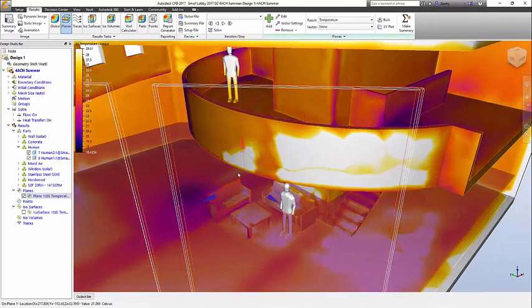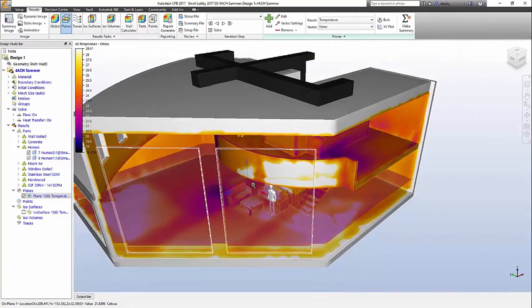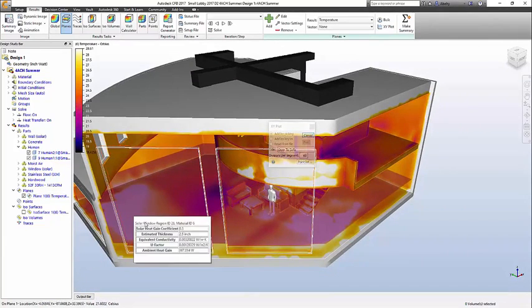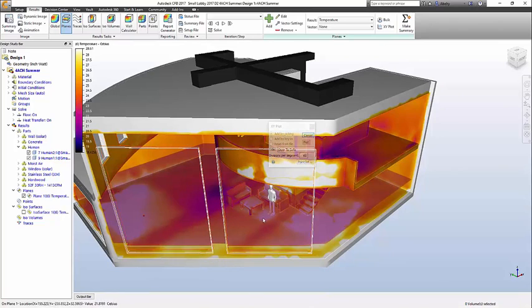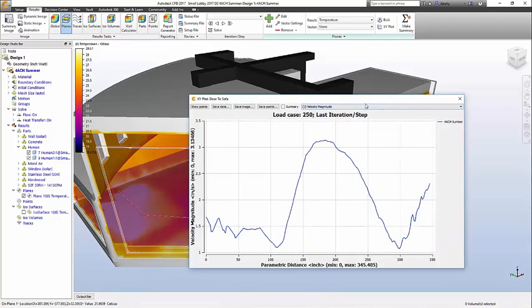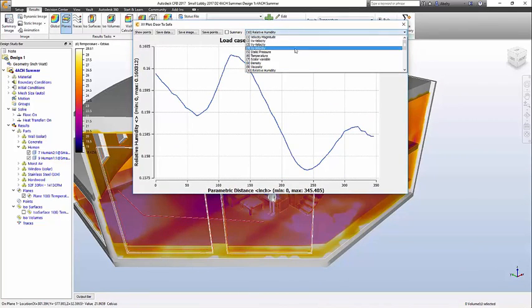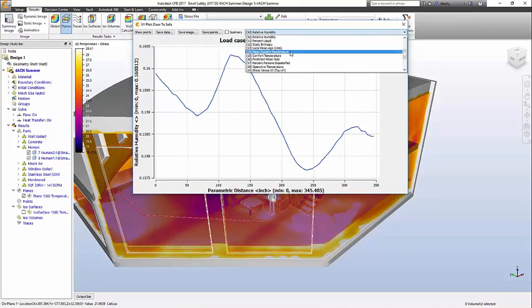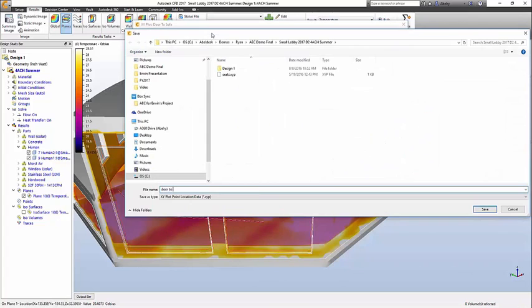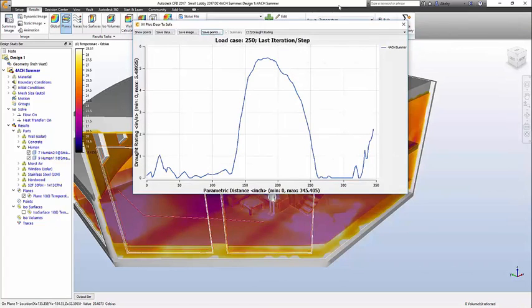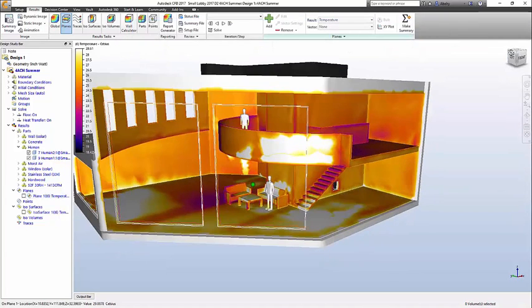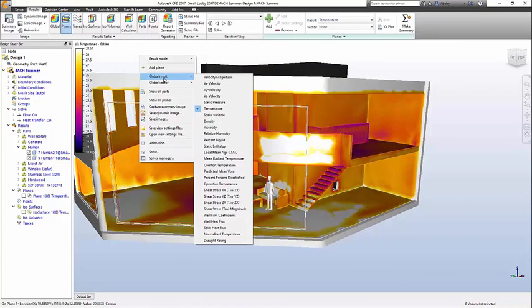What is the environment like as you enter through the front door and walk to the waiting area? To investigate this, let's create a data acquisition line. Select a few points, and you will see a red line in the corresponding temperature data. But you're not stuck just looking at temperature. In fact, you can look at all the data solved for on this pulldown. Velocity, relative humidity, draft rating, are ones I think you'll find the most useful.